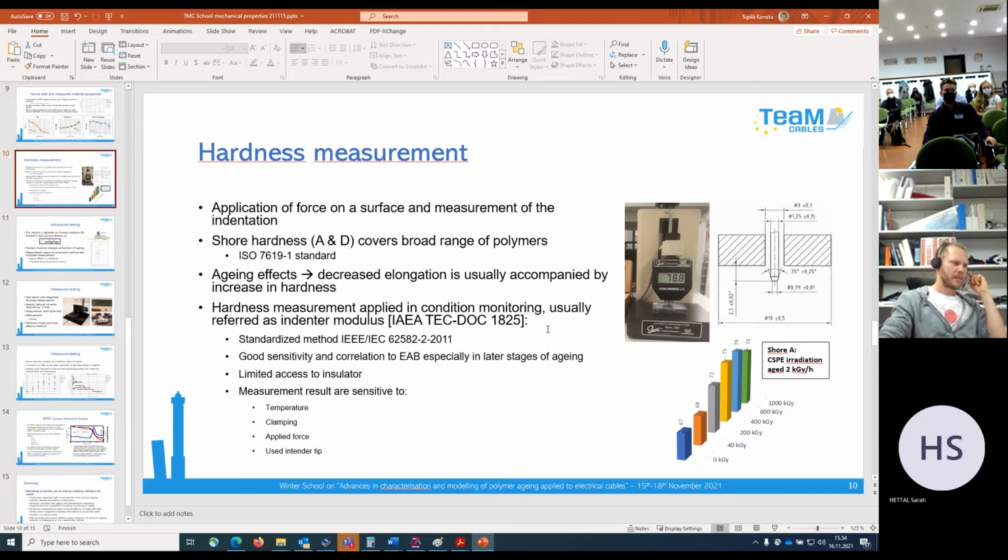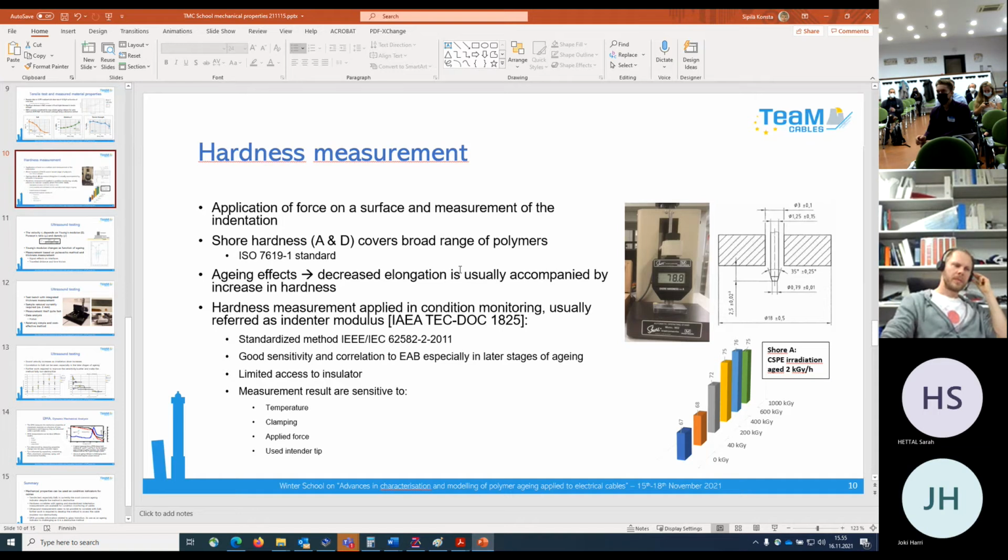And you usually measure that on the sheath, or do you also go into the insulation? No, for insulation. This is a function-relevant material of the cover. The sheath is only for mechanical aspects. But it is manageable to remove the sheath for a test at a certain position, maybe at a hotspot. Later, you have to fix it, for example by cutting and making a new connection. So you create a joint. Yes, one opportunity, but you need the authorities' approval and so on for sure. Otherwise, you will have a big effort. If you do it at a hotspot, it's representative for maybe thousands of other cables.